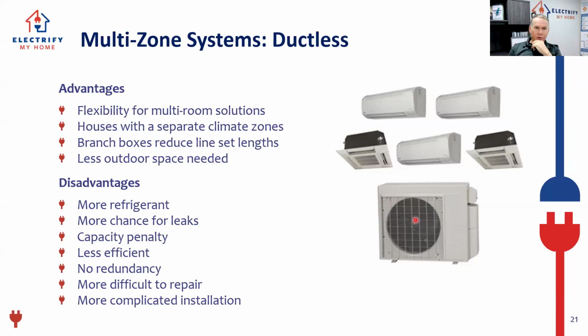That's great than putting multiple zones out there. But the disadvantages, like we talked about, way more refrigerant in these units. If there's ever a leak, we've done a lot more damage to the atmosphere, which a lot of people that get heat pumps in their houses are getting it because they're eco-friendly people and they say, "Hey, I want a system that's going to be good for the environment." And then we put one in that has 20 possibilities for leakage, and sometimes those things can leak for years.